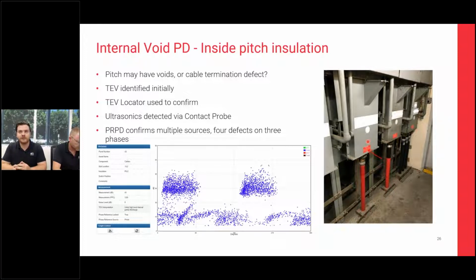And this is one of the few scenarios that actually goes against what I said earlier of you won't find those internal void sources with ultrasonic testing. But when we placed it on the outside, we could hear this particular discharge source buzzing or arcing, sparking. So this was just one of the scenarios where still doing that test was a good option.